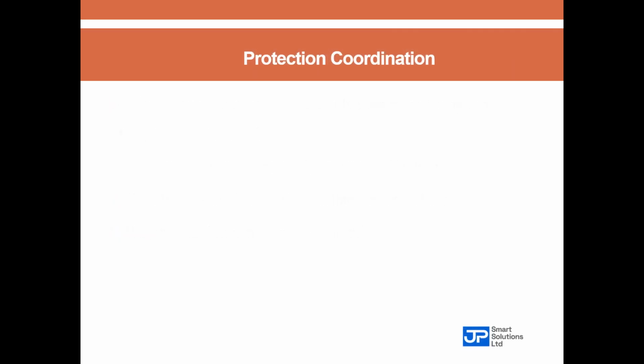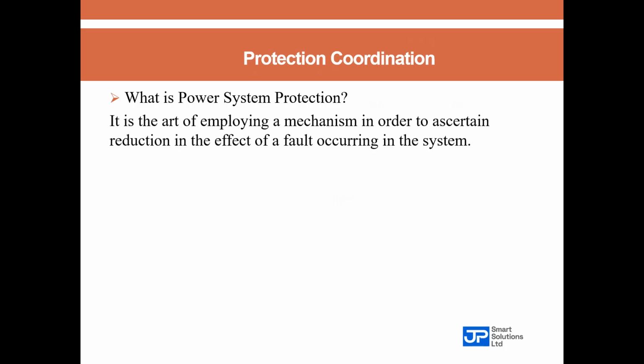Now, protection coordination. What is power system protection on its own before we talk about the coordination of the protection? Power system protection is the act of employing a mechanism in order to ascertain reduction in the effect of a fault occurring in the system. Misconception number one. People think power system protection is carried out to prevent the occurrence of a fault. That is wrong. In electrical power systems, faults are inevitable. So we can only reduce the effect, we can only mitigate the effect of a fault occurring in the system. So the fault must occur.